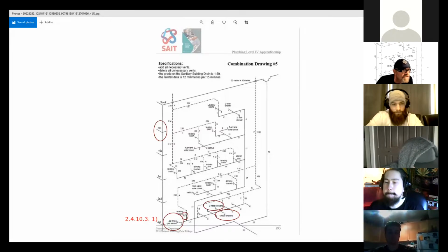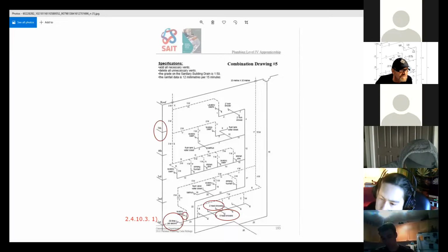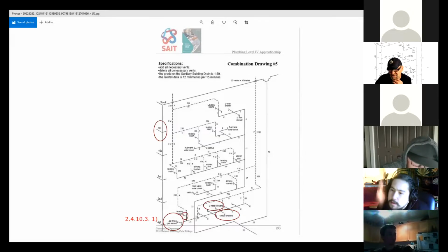So in this drawing, if you look where we dump these fixture units in, there is the lower end of this vent stack, including the wet part. So I'm going to go up and you guys tell me where it ends. Well, outside air, there's the developed length of that vent stack. You'd have to count the 15 meters, the 4 meters, the 3 meters, the 5 meters, and 5 meters, all the way down to the bottom. That would be its developed length. So yes, the developed length of a vent stack is lower end to outside air.